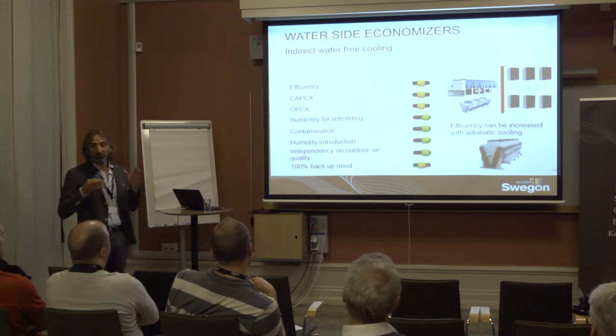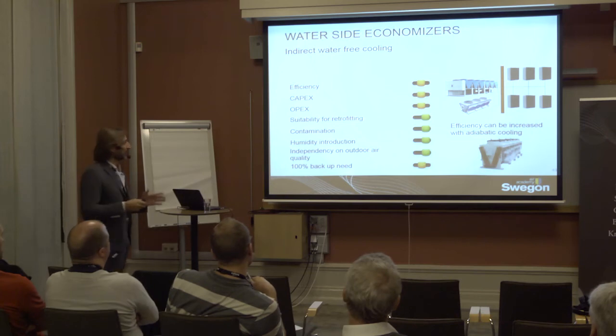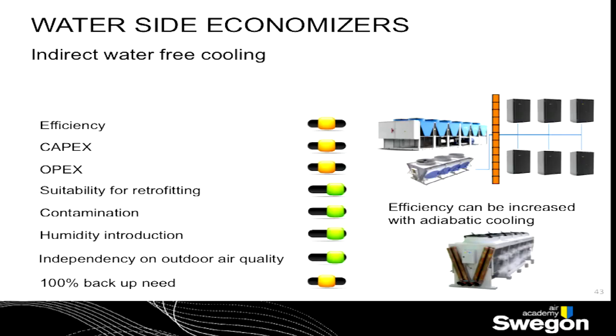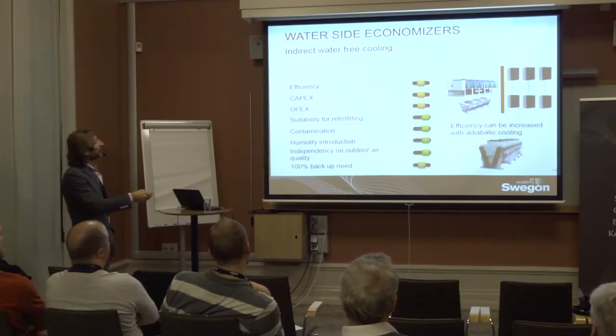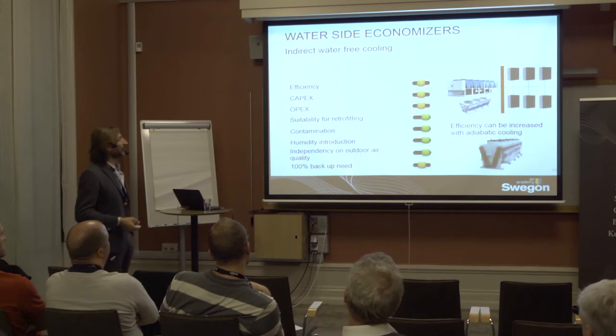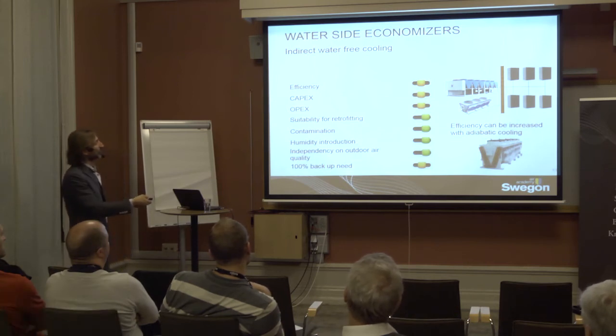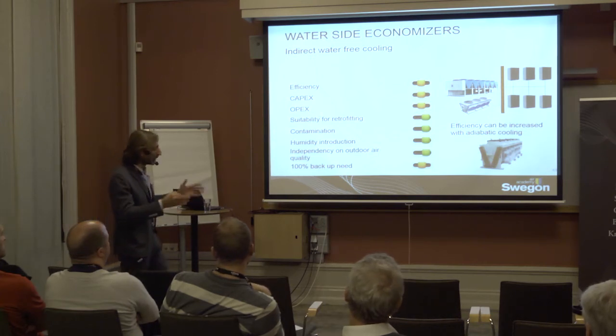But if we have to take care about the indoor conditions, and if we have to avoid the mixing of air, we are forced to go for an indirect free cooling system. It can be based on water with a chiller combined with a free cooling section, or, let's say, a dry cooler that can be equipped with an adiabatic system that increases the efficiency of the system. And of course, in this case, we have to accept a lower level of efficiency because we have to cool down the water, but we avoid completely the mixing of the air. So we maintain the data center completely closed, okay, and we do not have to take care about pollutants or humidity.